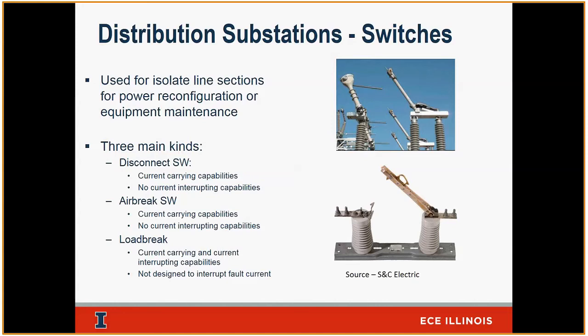Okay. Another thing you'll find inside substations, we kind of talked a little bit about it, are switches, right? And there are types of switches. Mainly the switches are used to isolate the equipment and redirect power flow. We talked about wanting to take this transformer, for example, for maintenance. So what our guys will do is they will open these two switches to de-energize the transformer, do whatever work you need to do on it, refill the oil, do whatever maintenance you have to do on a transformer. And then you use another switch to redirect energy and have these loads fed by the other source.